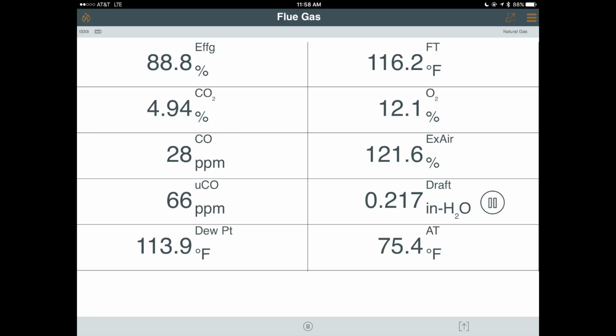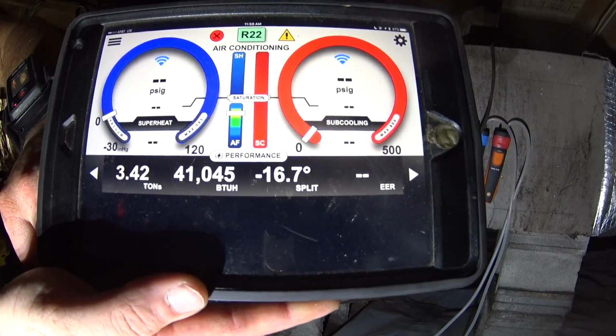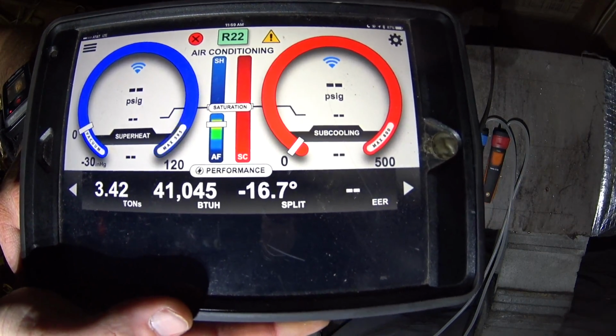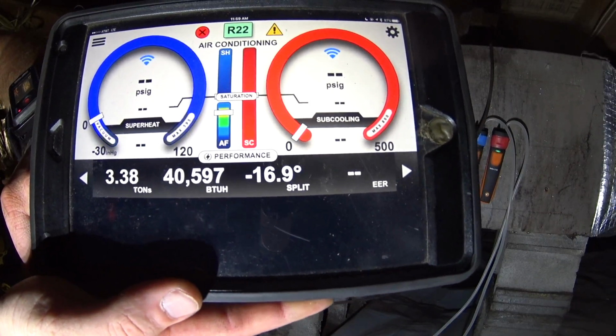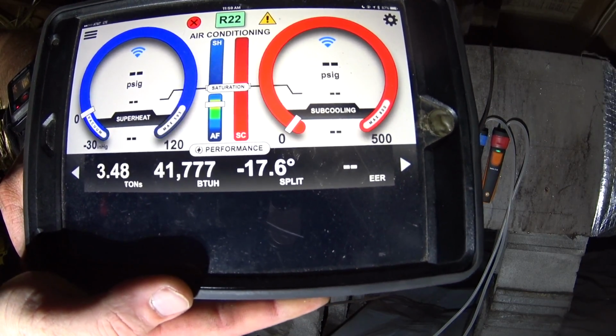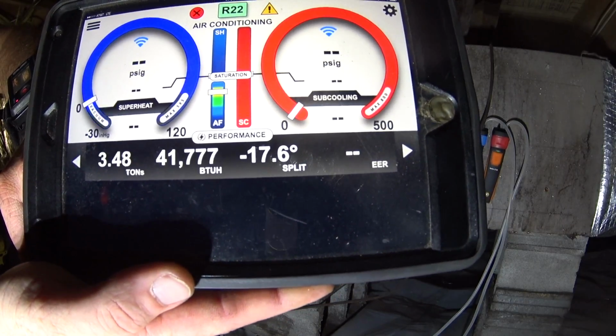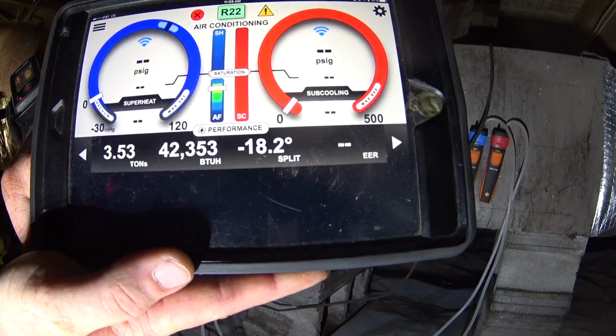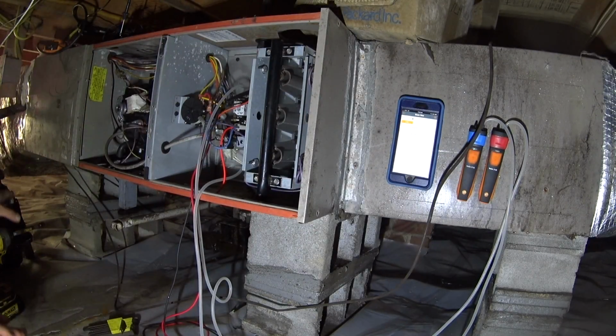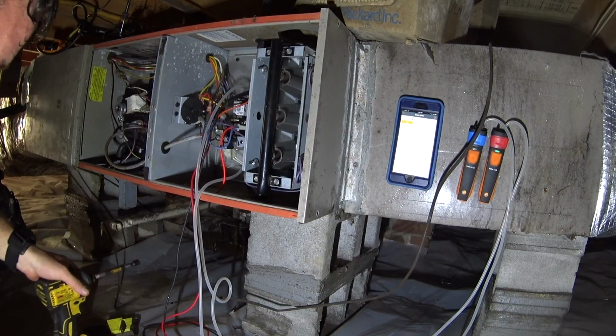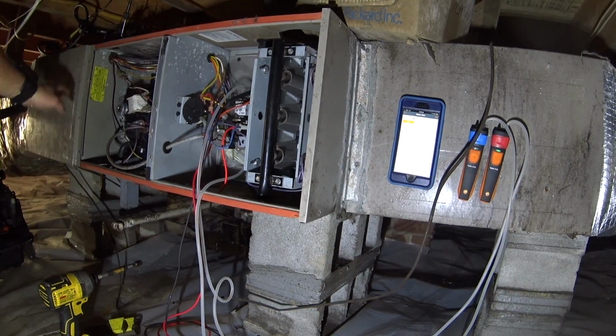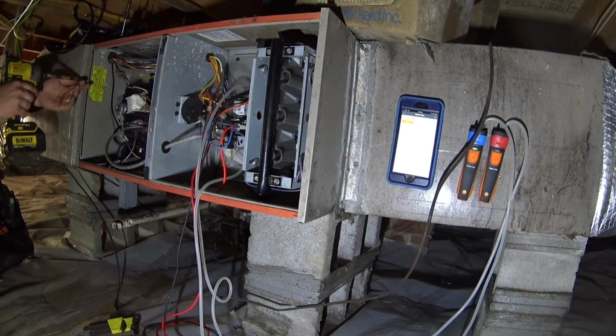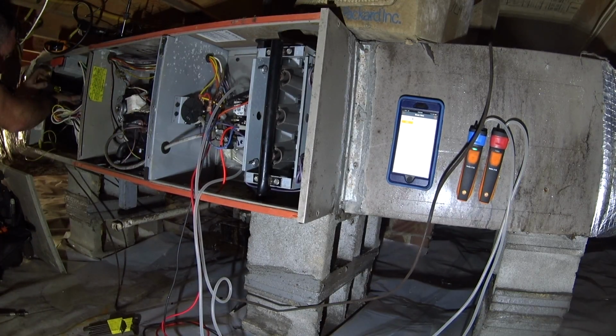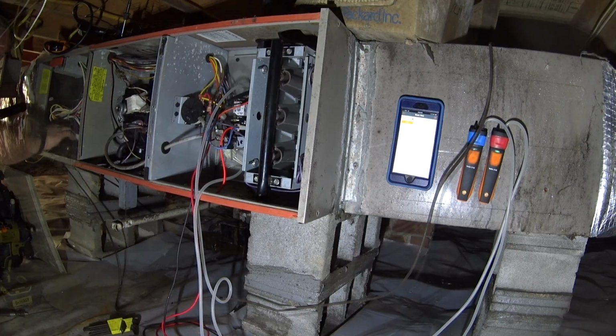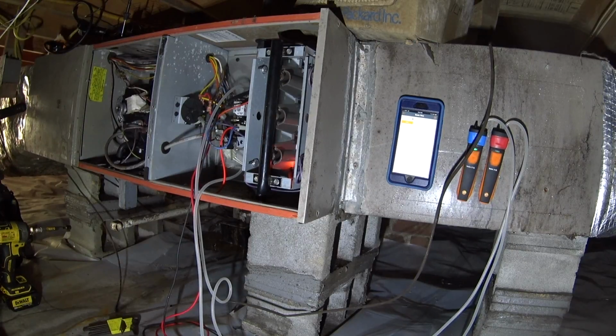We'll see what the temperature rise looks like. One thing that I would like to see iManifold do is allow a gas heat profile, because as it is, it shows a negative temperature split because it's expecting to see a temperature drop, not a temperature rise. We got 18 or 19 degrees. Combustion is still lean, of course. I'm going to see if I can get second stage to bump up, but it'll probably drop out. And I've given up on trying to keep myself dry. At this point, I'm kneeling in a puddle of water.